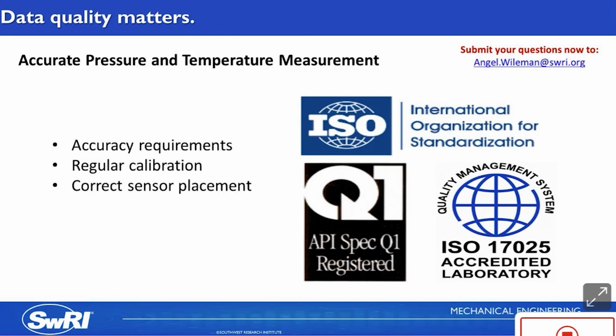Make sure you review the standards and you place all of your instrument sensors correctly, especially with the thermocouple placement that we discussed earlier. I would also suggest using additional instrumentation as references. You will already have reference measurements for temperature if you follow the standard correctly, but think about adding an extra pressure transmitter to the stand as well.